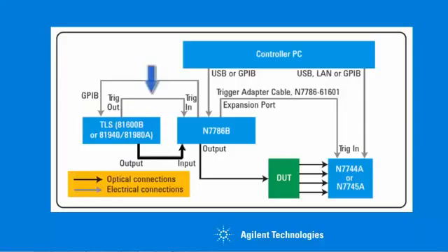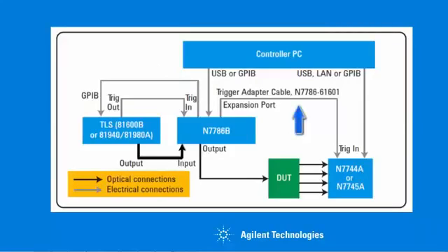There's a GPIB connection between the N7786 and the tunable laser. Additionally, we have a trigger connection. There's a BNC trigger output on the rear of the tunable laser, which is connected to a BNC trigger input on the N7786B. And there's also a trigger connection between the N7786B and the multiport power meter. This is a special cable that ships as part of the N7786B.